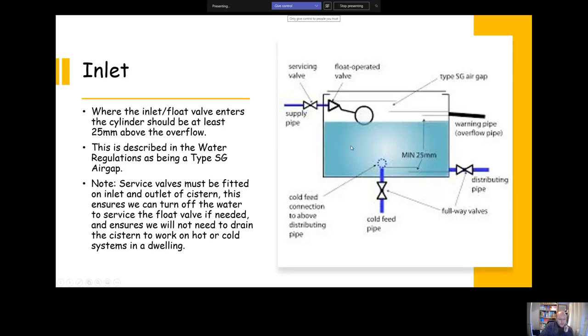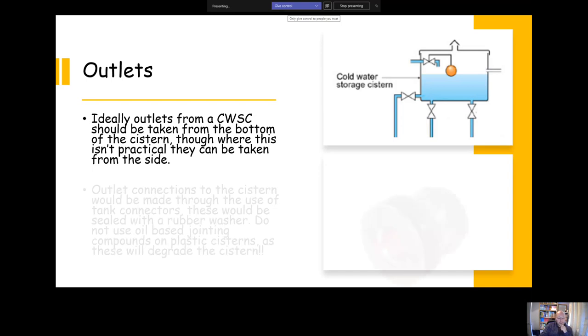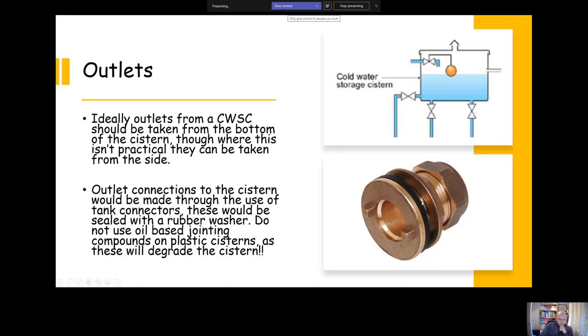For outlets, ideally, this is a bit of a tricky one because it's not something that people always do in real life, but according to the water regulations, ideally we should take all connections from the base of the system. This isn't always practical. In reality, most people will take their connections from the side, but it's recommended in the water regulations that we take all of our connections from the base. This is a tank connector here and this is what we'd use to make our connections. It would be sealed with a rubber or a plastic washer. Don't use oil-based jointing compounds because they will degrade the system. Anything oil-based will break down plastic.